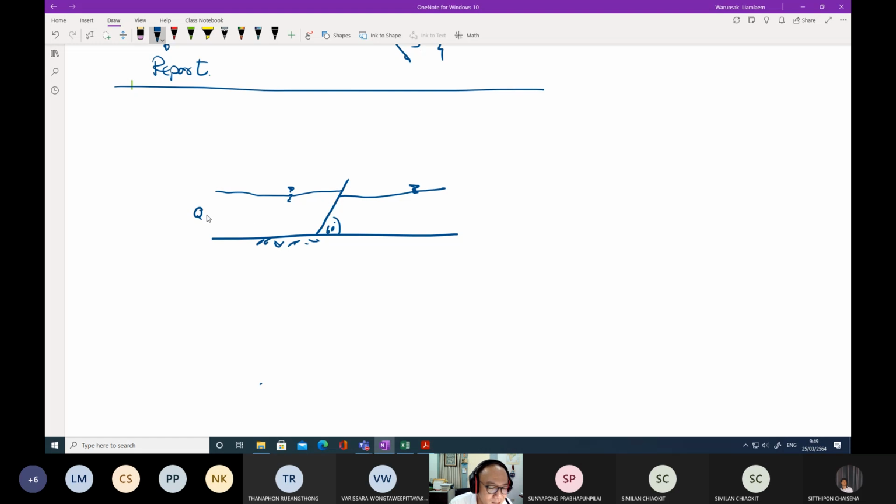So this is the flow, and this is the direction of the flow. Water passes through the opening area of the screen, and the water level in front of the screen is given as H1, and the water level after passing through the screen is given as H2. So there is a difference between the water levels in front of and behind the screen.